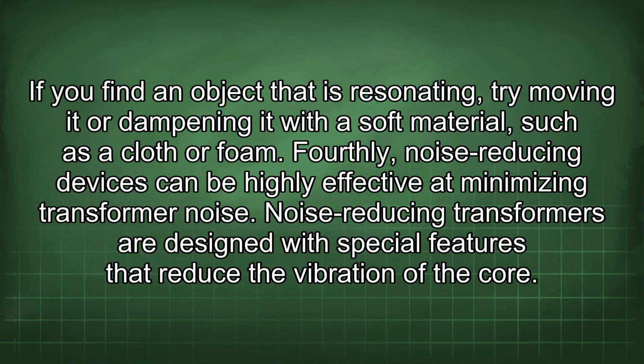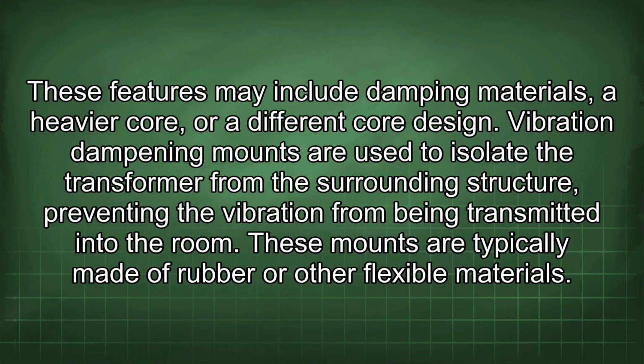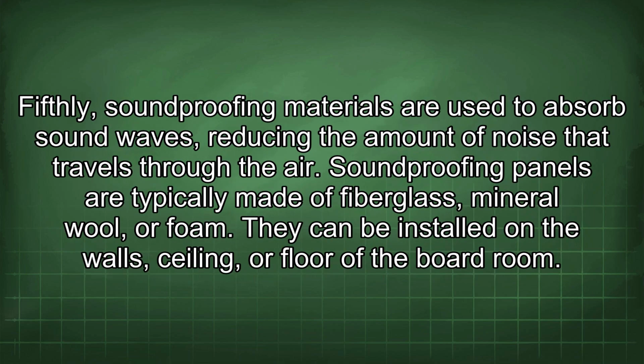Noise-reducing transformers are designed with special features that reduce the vibration of the core. These features may include damping materials, a heavy core, or a different core design. Vibration dampening mounts are used to isolate the transformer from the surrounding structure, preventing the vibration from being transmitted into the room. These mounts are typically made of rubber or other flexible materials. Fifthly, soundproofing materials are used to absorb sound waves, reducing the amount of noise that travels through the air.